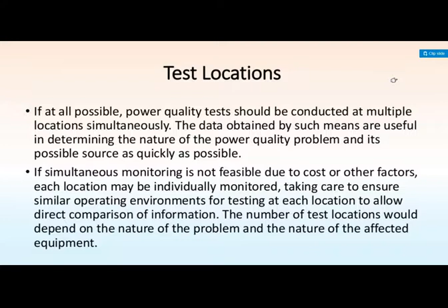If the power quality problems are observed at location C and not at B, it is not necessary to monitor A. On the other hand, if the problems are noticed at C and B, then location A should be tested, as well as location D if necessary. The experience of the power quality engineer becomes important when trying to resolve the different scenarios. So this is the basic example of the test location.